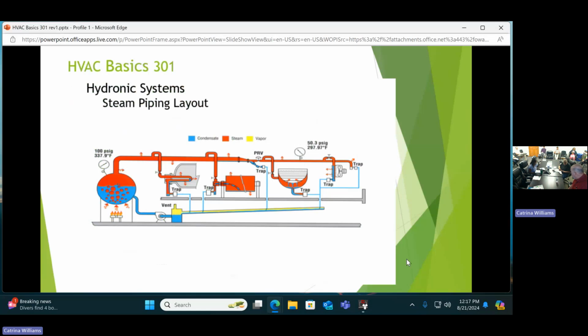Any questions? Does the water have to be treated? Yeah, typically they do because of the mineral content. They'll have a water treatment system in between here and that boiler. Okay. And on the makeup water, the boiling point is going to be different depending on the elevation. Yeah. And you have to treat steam because it can develop into an acid called carbonic acid, and that's part of what they treat for. But you are correct, all these temperatures are based on sea level conditions. Right. Standard air. Right. The boiling temperature changes as you're climbing in altitude. So ask questions. That's what we're here for.